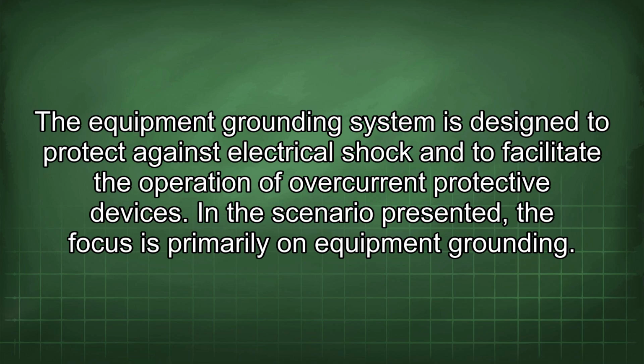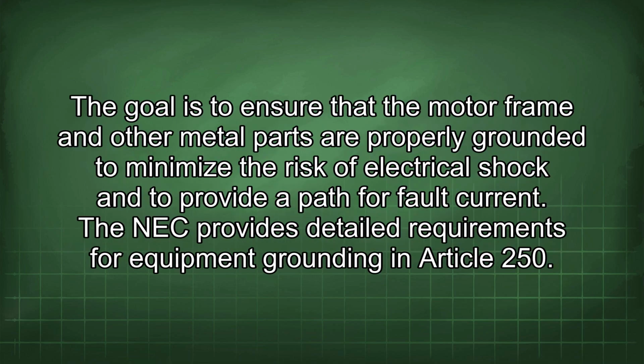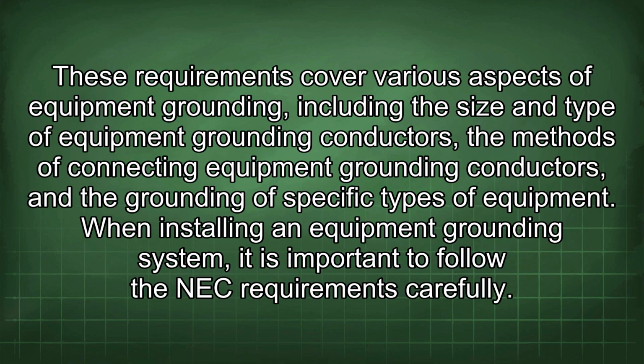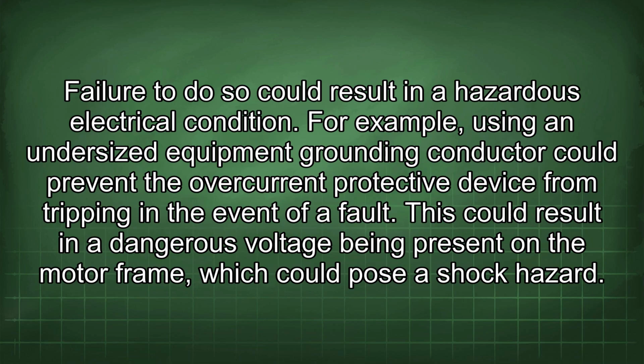In the scenario presented, the focus is primarily on equipment grounding. The goal is to ensure that the motor frame and other metal parts are properly grounded to minimize the risk of electrical shock and to provide a path for fault current. The NEC provides detailed requirements for equipment grounding in Article 250. These requirements cover various aspects of equipment grounding, including the size and type of equipment grounding conductors, the methods of connecting equipment grounding conductors, and the grounding of specific types of equipment. When installing an equipment grounding system, it is important to follow the NEC requirements carefully. Failure to do so could result in a hazardous electrical condition. For example, using an undersized equipment grounding conductor could prevent the overcurrent protective device from tripping in the event of a fault.